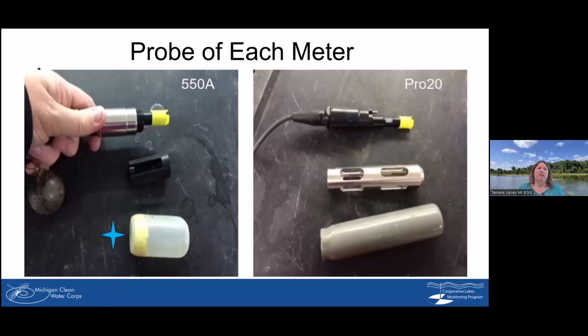Here's what the dissolved oxygen and temperature probe looks like for both the 550A and the Pro 20. They're very similar. You can see a yellow cap. That is where the dissolved oxygen probe is, and the cap is a membrane that goes on top and needs to be changed every year. If you have your own meter, you should be changing this membrane at least once a year. And also, if your meter is not calibrating, this is the first thing to check. This is a metal cage, or the older ones have a plastic cage that goes over the top to protect that membrane. And then there's a plastic cap that has a sponge in it, and that sponge is important. We want to keep it moist, not standing water. It just needs a few drops to keep moist so that this membrane stays moist and keeps calibrating for you.